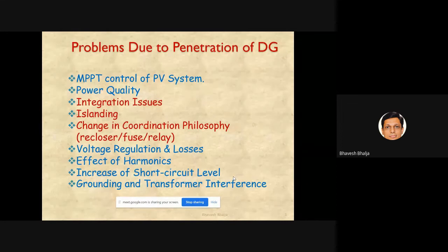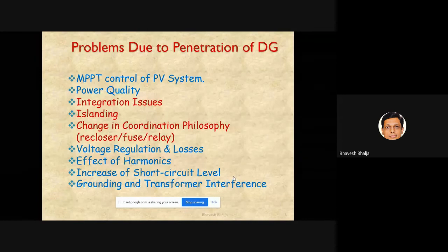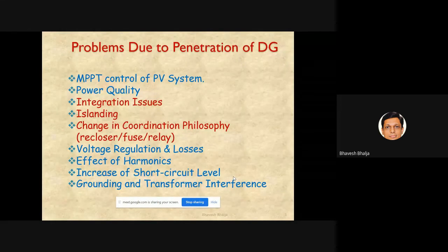The next issue is grounding and transformer interference. When no DG is connected, the utility or distribution substation has some type of grounding, and a transformer as well, maybe delta-delta or star-star. Now, as and when you connect a DG, grounding plays an important role. Depending upon whether your generator is delta connected or star connected, accordingly you have done the grounding, whether resistive grounding, effective grounding, non-effective grounding, or some other type.